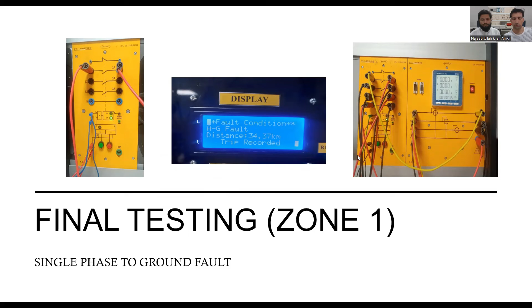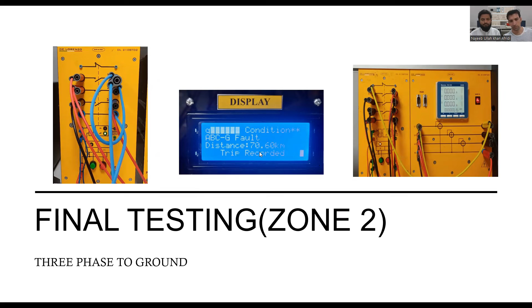And then we give a three-phase to ground fault in zone 2, and our relay takes a 350 millisecond delay and then generates a trip signal, and our breaker trips. As we see, the fault is isolated, and it also tells us the distance at which the fault occurred, 70.60 kilometers. Then we give a double phase to ground fault in zone 2, and the display panel shows in which phases the fault occurred, and from here we can see that the fault is isolated.